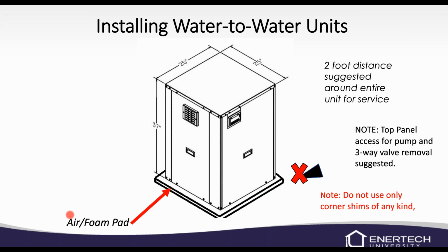Don't set the unit on corner shims or corner blocks. We've got to support the whole base of that unit. If we don't, what will happen is that metal in the bottom of the unit will start to weaken, and then the whole bottom could fall out of the unit. So no shims of any kind.